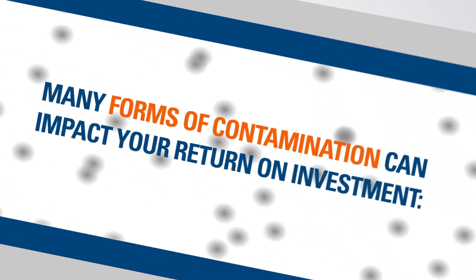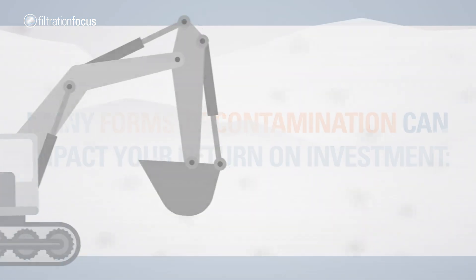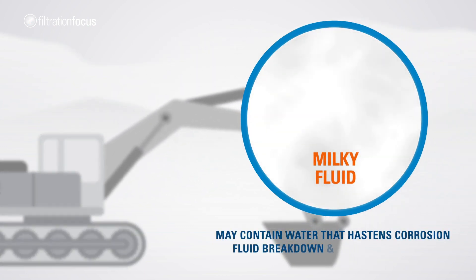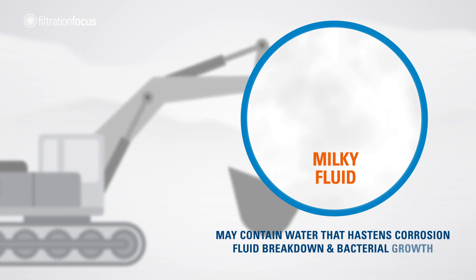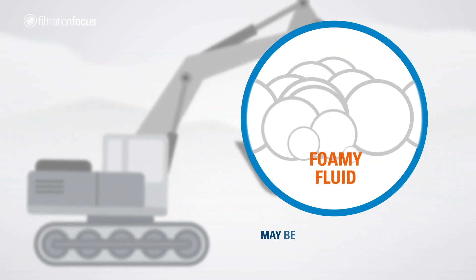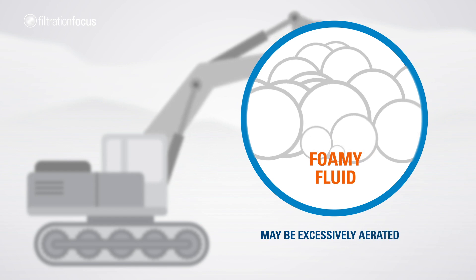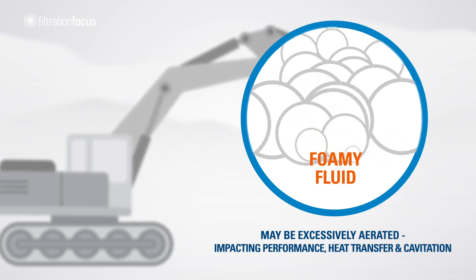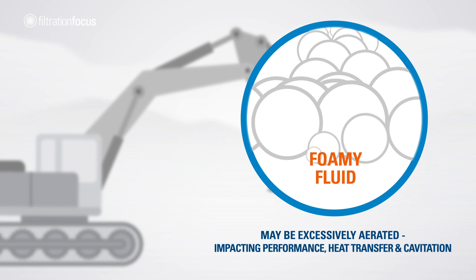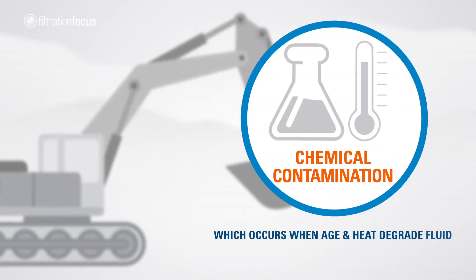Milky fluid may contain water that hastens corrosion, fluid breakdown, and bacterial growth. Foamy fluid may be excessively aerated, impacting performance, heat transfer, and cavitation. Chemical contamination occurs when age and heat degrade the fluid, or if incompatible additives are mixed.